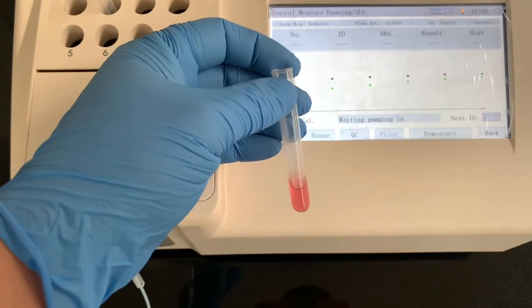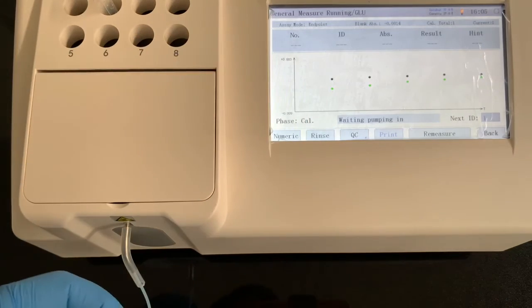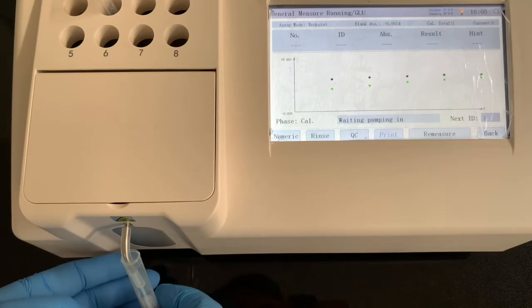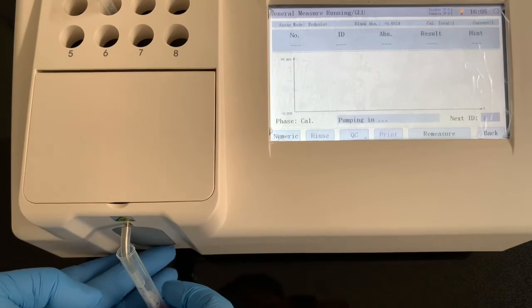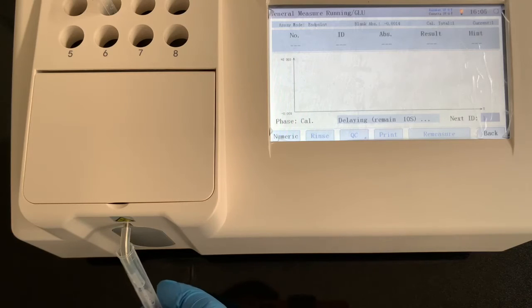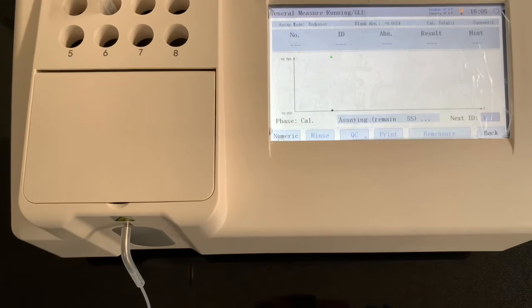This is prepared calibration tube. Press gray round button to aspirate. After delay and measurement, analyzer will show new calibration factor. And calibration is finished. Our new factor is 22.96.